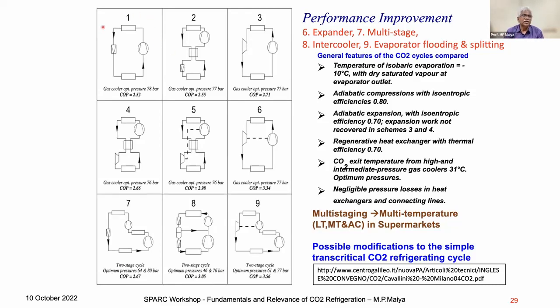You can see from here the simple system, and then also the expander, and the double-stage compressor with intercooler. This is another method. Two-stage compression with intercooler also increases the COP. Compared to this and this, you can see almost a 40% increase in COP, 2.5 to 3.5. There is a 40% increase from here to here. That's remarkable. We have to use all the techniques. Then evaporator flooding is possible, and splitting of the evaporator. That also increases the COP.